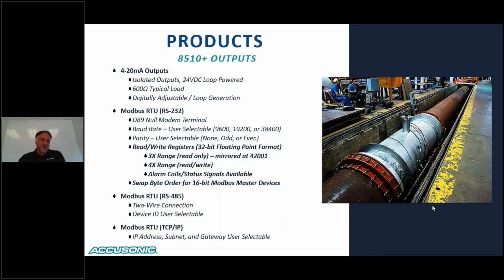The 3x range is designed for read-only, but we do mirror that in the 4x range for those customers whose Modbus masters can only communicate in the 4x range. The beginning portion of that 4x range is the read and write, so that would be your parameters, and the read-only registers would be your variables, path gains, flow rate, volume, etc. And if you are a customer who has a 16-bit Modbus master device, you basically just have to swap the byte order for Little Endian mode and to convert it into 32-bit floating point.